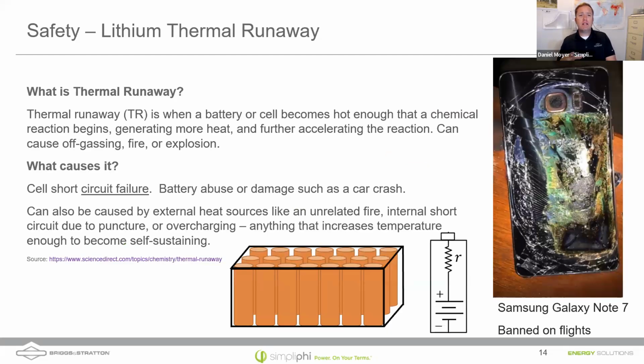Thermal runaway is essentially a chemical chain reaction where batteries can spread heat to other adjacent batteries, and it's not necessarily caused by flaming, but by heat. If you want to extinguish one of these thermal runaway events, depriving it of oxygen isn't always going to work. You need to cool the batteries, which requires a lot of water or something similar. If you think about how these batteries or energy storage systems are constructed, they're usually inside a case, inside another metal case, and it's really hard to get at with water or cooling.